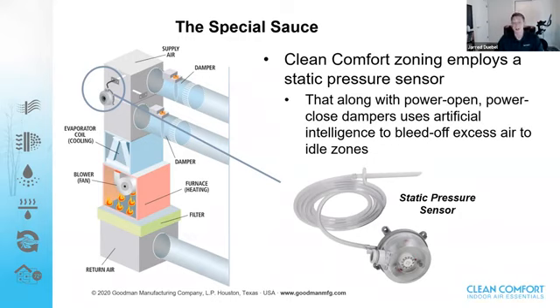First of all, it saves on time, money, and the effort of having to go around and take static pressure readings and getting that bypass damper set just right. With the ESP system, again, you get the static pressure sensor. By our studies, we have determined that at 0.35 inches of water column, which is where we map how we monitor static pressure, systems start to get noisy. So we preset our static pressure sensor from the factory at 0.35 inches of water column. However, it is fully adjustable, so the technician can adjust it up or down if they'd like to, but we're simply saying that is where that threshold is.